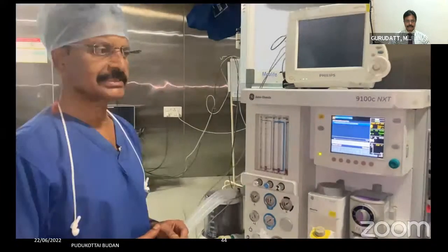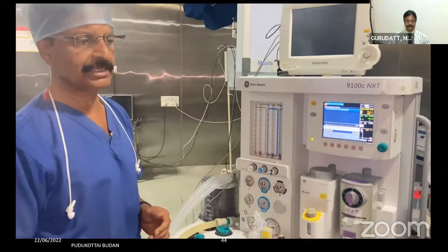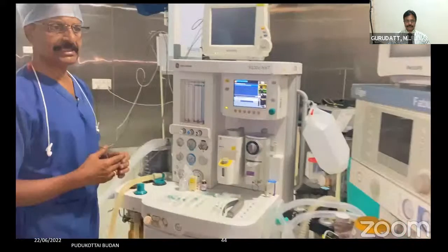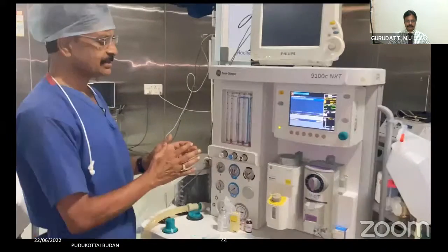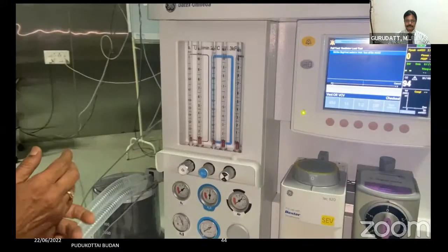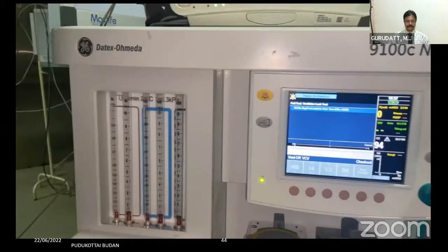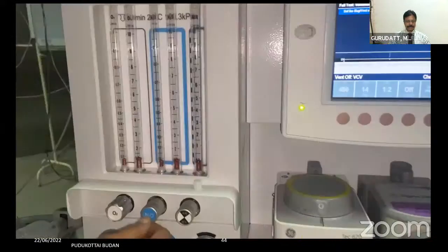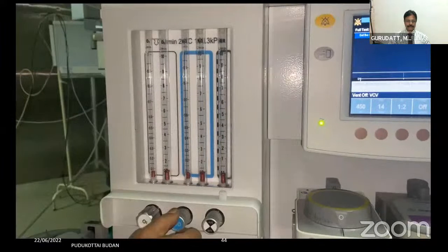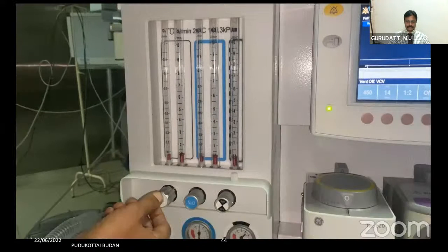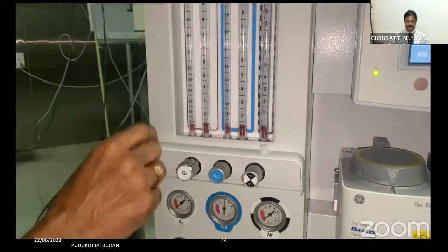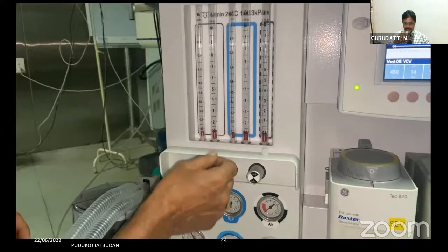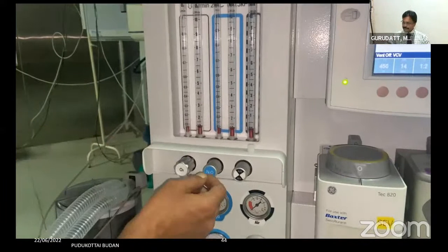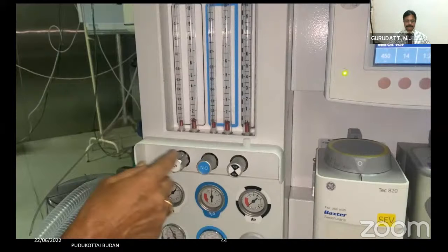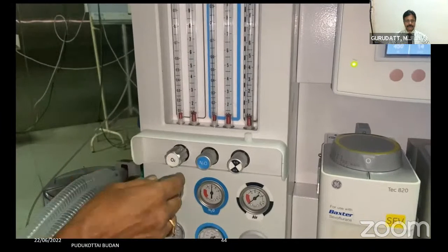So how do you differentiate whether a particular workstation has the Link-25 or the SORC type of hypoxic guard? It's a very easy thing. I'll demonstrate how to know whether it is Link-25 or not, because the GE machine has Link-25. You just have to rotate the nitrous oxide flow control knob. When you rotate it, if the flow control knob of oxygen also rotates, then it is Link-25, because you cannot open only nitrous oxide as the hypoxic guard is there. Once you try to open the nitrous oxide, the link gets established between the nitrous oxide and the oxygen sprockets, so the oxygen flow control knob also rotates.